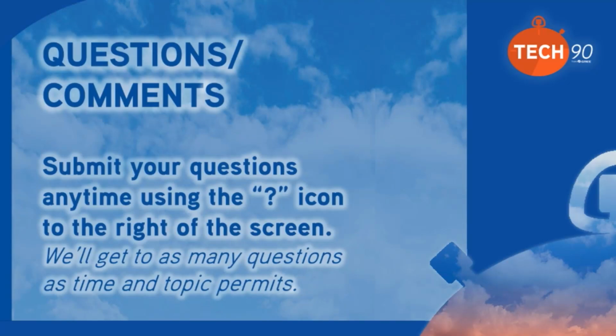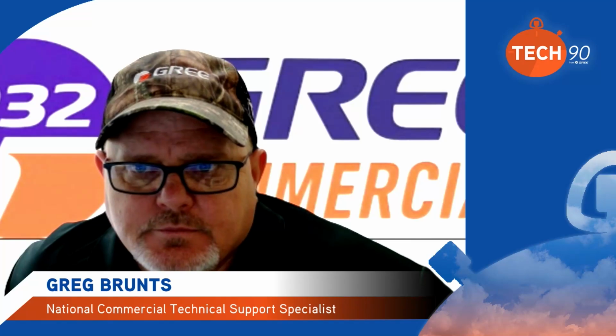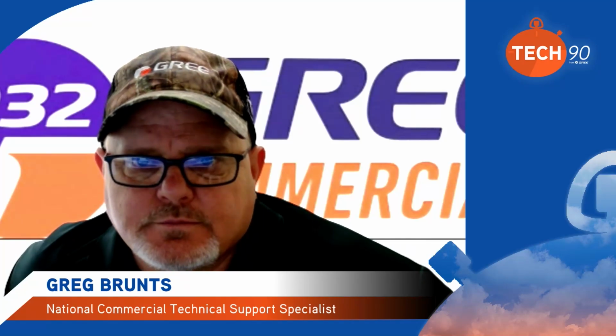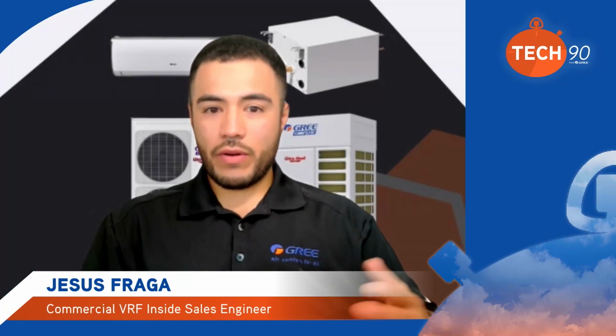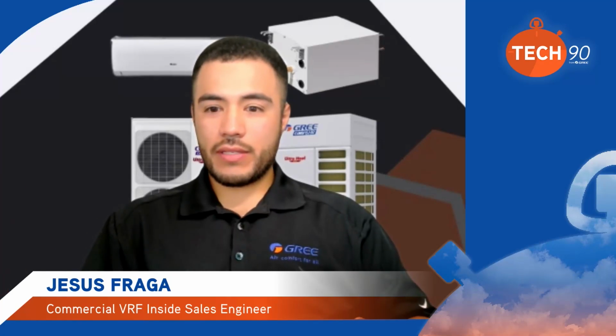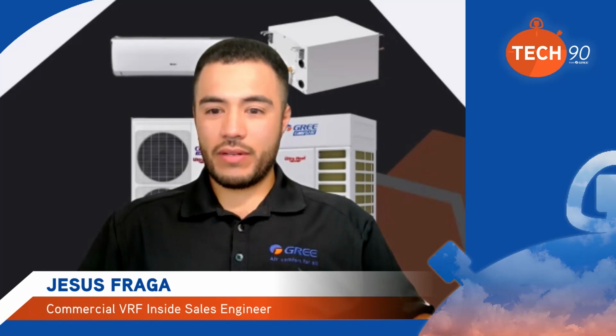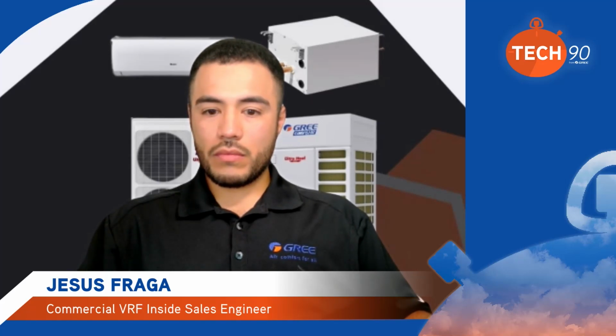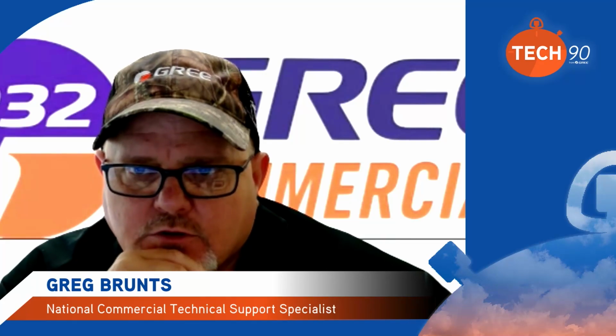I would. You don't have to use an AC disconnect. It could be a 2-pole switch, because that gives you the ability, let's say you've got 4 indoor units and you need to service one of those 4, and we still maintain over our 50% connected capacity, I can turn the power off to that one head and work on that one head and allow the rest of the system to still function. I don't have to kill the power to all of the indoor units. Well, I think that's crucial to mention, because I know I've worked with equipment in the past where you shut down one interior unit, and the whole system is just out. It's not functioning. So that's another key feature of the MultiPRO product. As long as we maintain 50% connected capacity, the outdoor unit can still function.